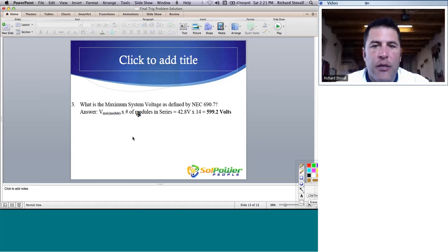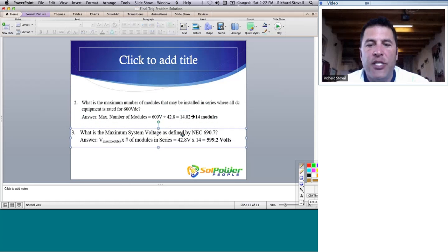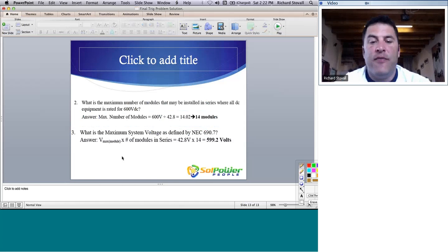And I'll just slap this one in here. It's the same. No change there. What is the maximum system voltage as defined by 690.7? Okay. And the number of modules in series times the maximum voltage that we calculated for, 42.8 volts.